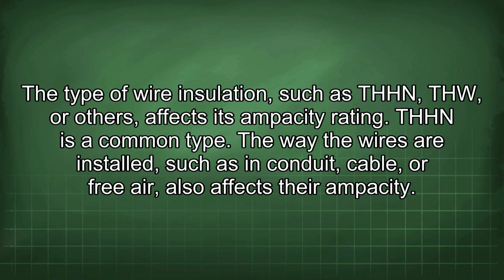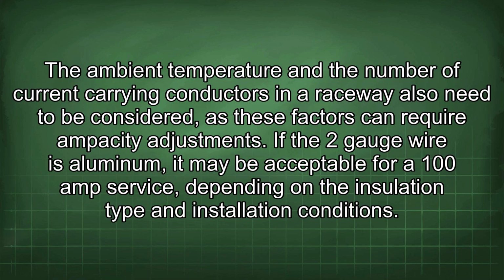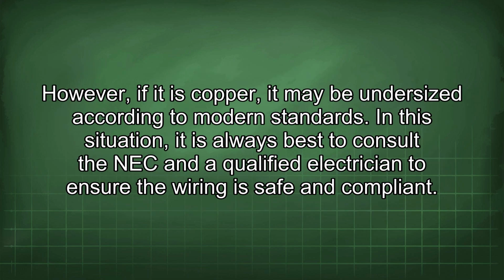The type of wire insulation, such as THHN, THW, or others, affects its ampacity rating. THHN is a common type. The way the wires are installed, such as in conduit, cable, or free air, also affects their ampacity. The ambient temperature and the number of current-carrying conductors in a raceway also need to be considered, as these factors can require ampacity adjustment. If the 2-gauge wire is aluminum, it may be acceptable for a 100 amp service, depending on the insulation type and installation conditions. However, if it is copper, it may be undersized according to modern standards.